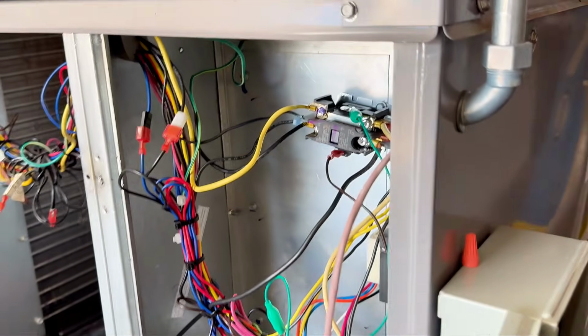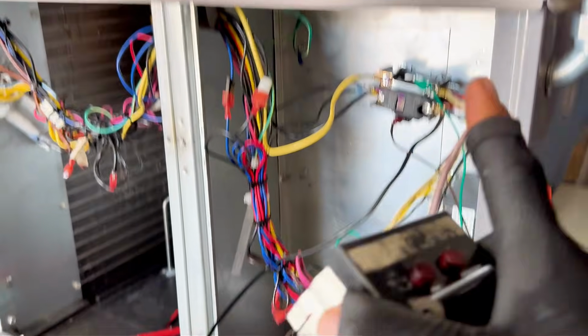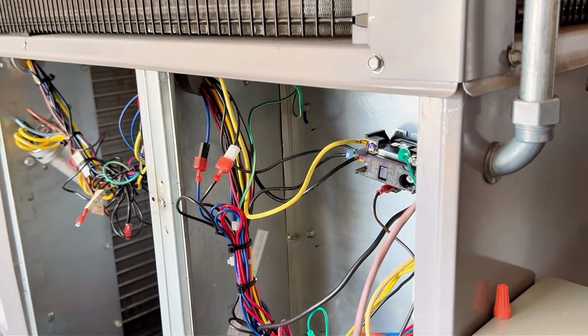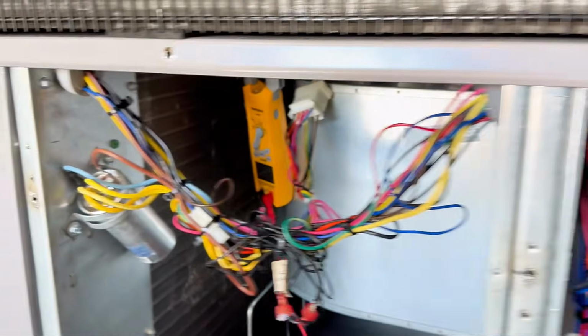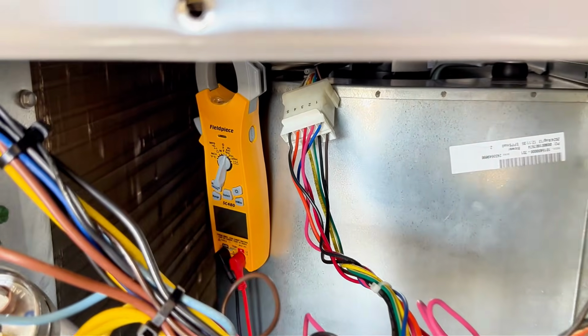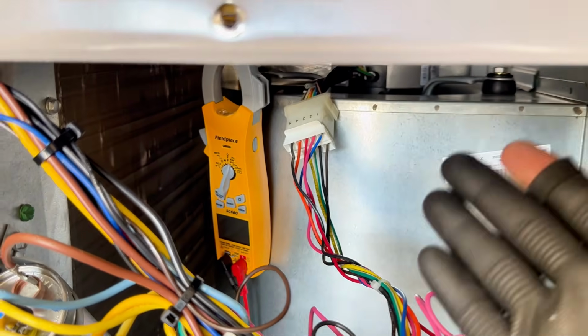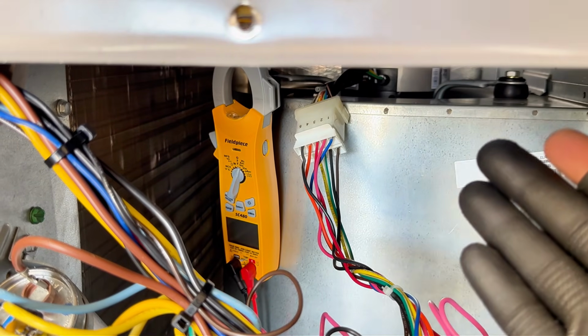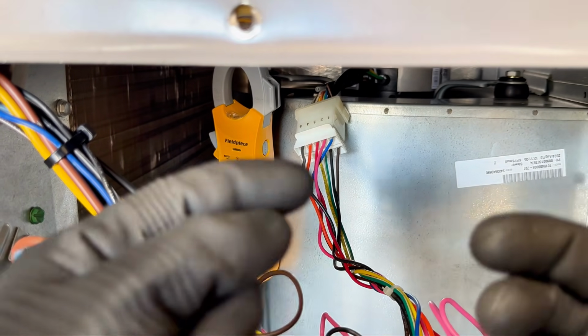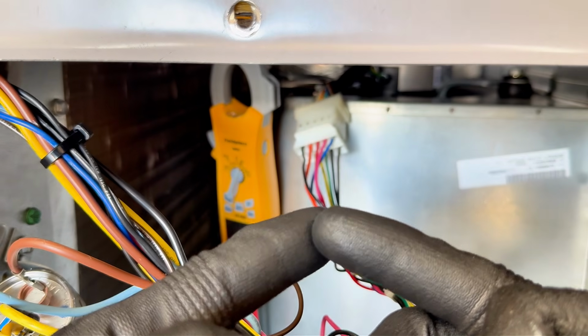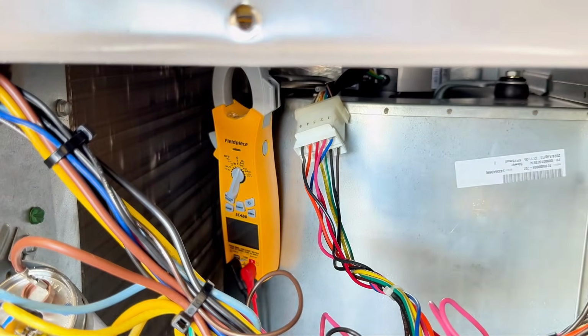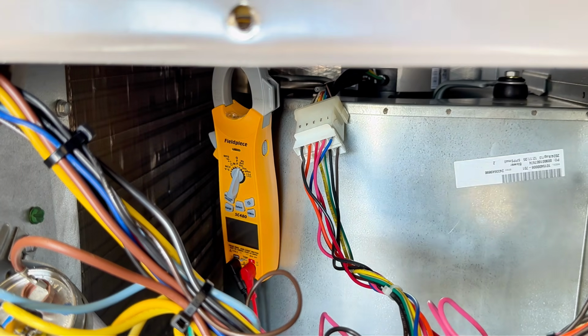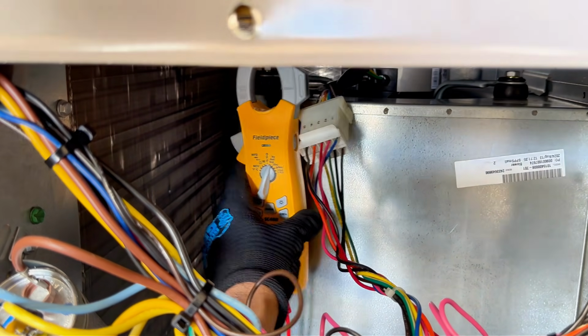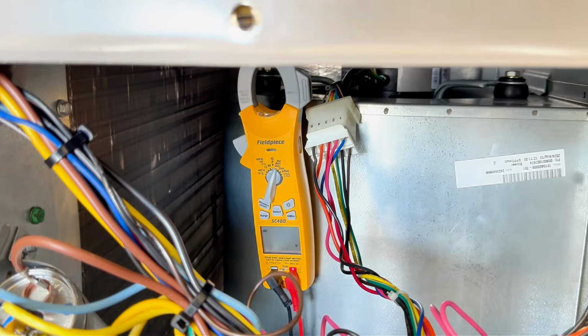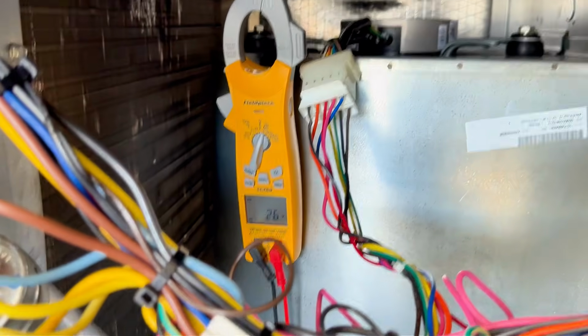I'm gonna go ahead and call for cooling. I do have it jumpered so that we don't have to wait for the thermostat. Okay, I just heard it turn on. So let's say you go to a job and you're calling for cooling and it's not spinning, right? How do you confirm if it's a bad motor or if the board is not sending the appropriate voltage? How you would check it, you have to put your meter on voltage, right? So let's go ahead and get a little bit closer right here.